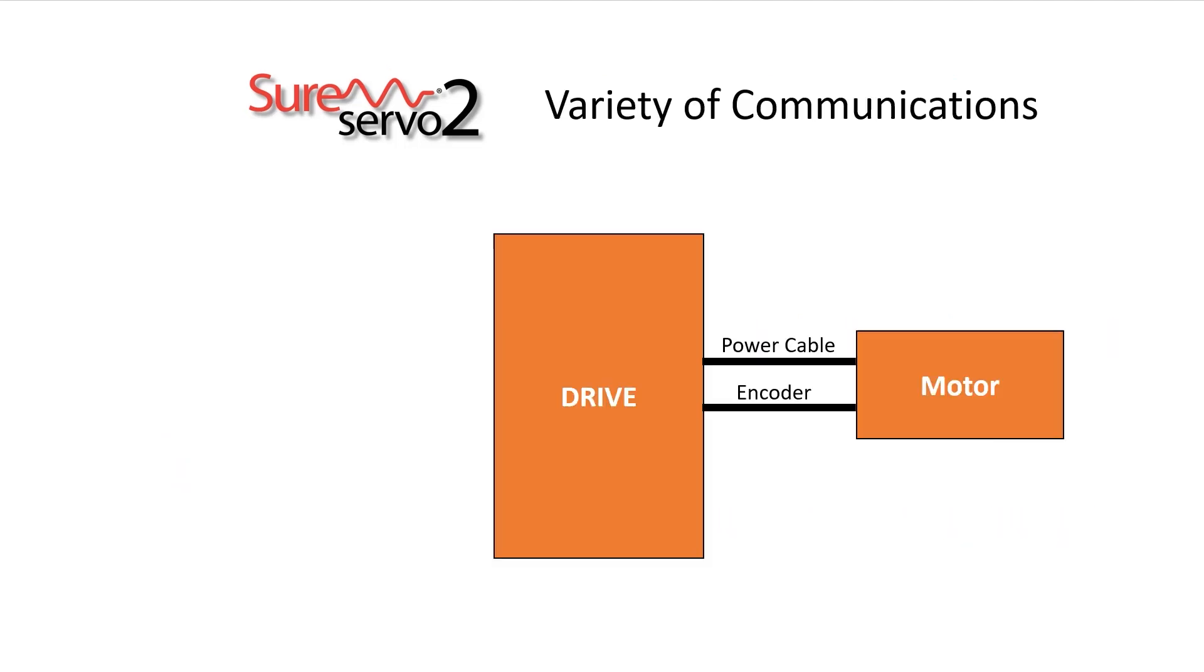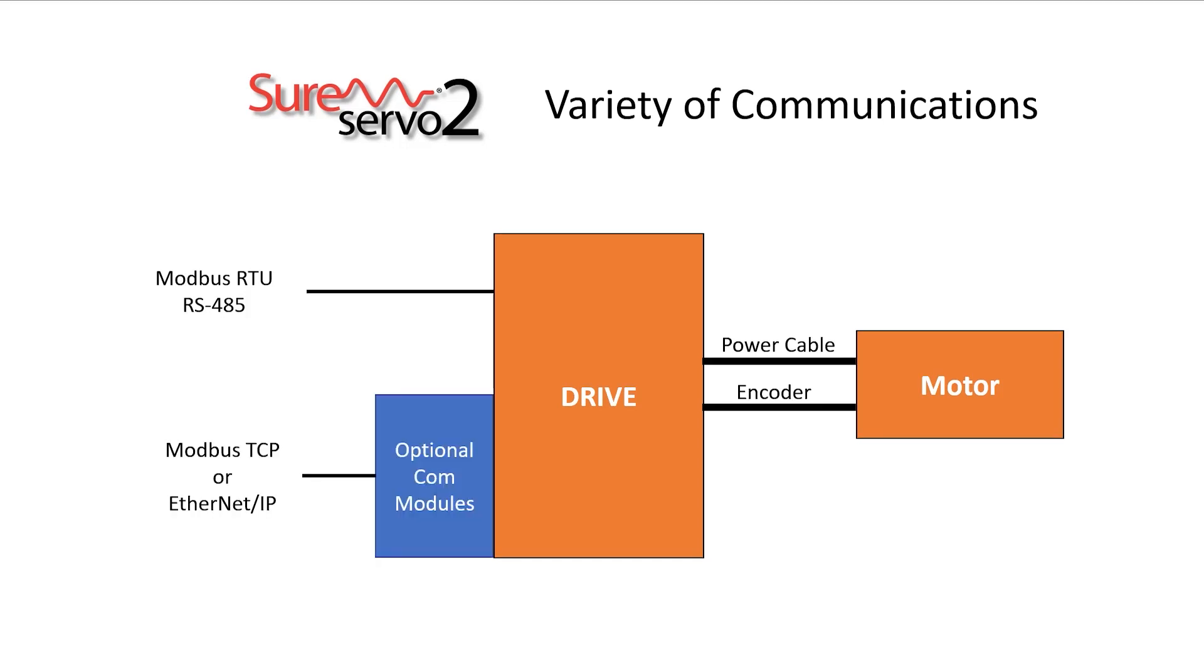Of course being able to communicate with a drive is just as important as making it do something, so every SureServo 2 drive has Modbus RTU via RS-485 built in for cost effective communications. And you can add Modbus TCP and Ethernet IP with optional expansion modules.